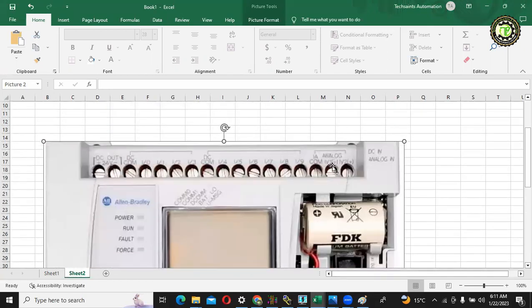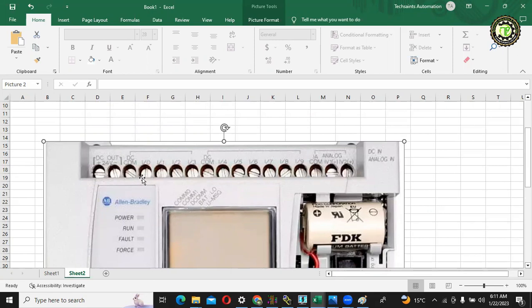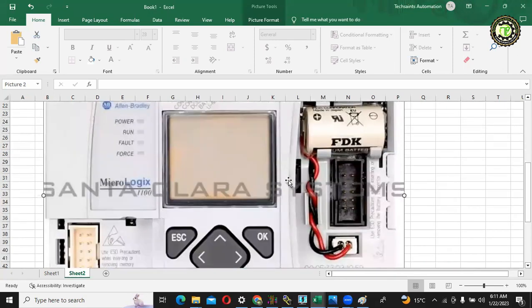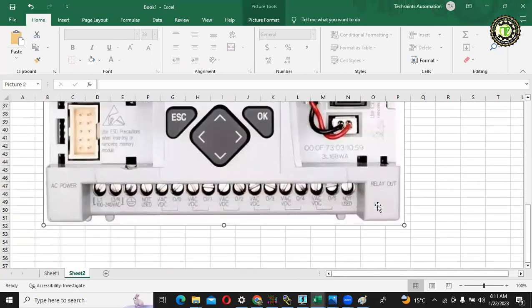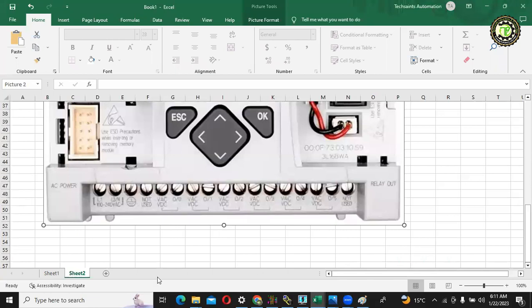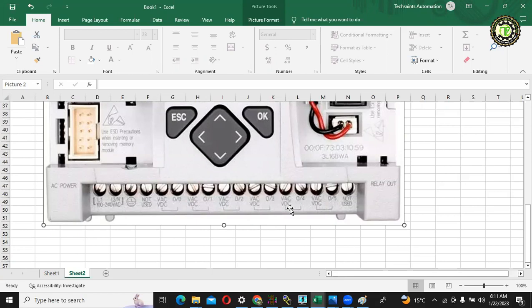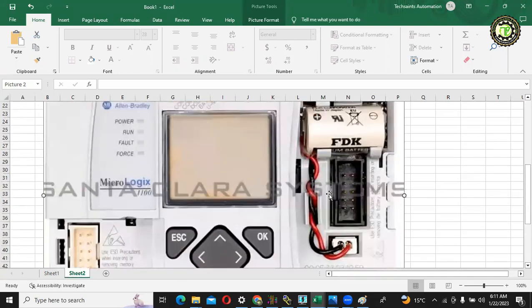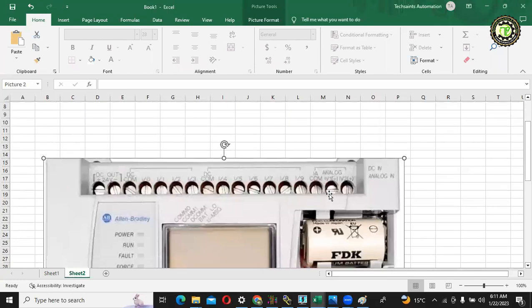From here I can give two analog inputs, this one and this one, and this is the common for analog inputs. These are the digital inputs. This PLC has relay output which is common for everyone. If we give AC volt here we will get AC voltages from here. If we give DC voltages here we will get DC voltages here because this PLC is relay type, and we can operate 110 AC voltage devices and 24 volt DC devices on a single CPU.